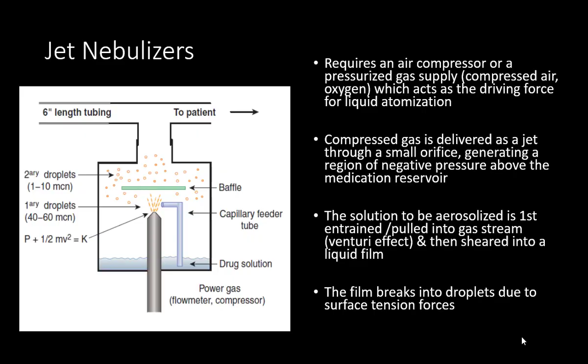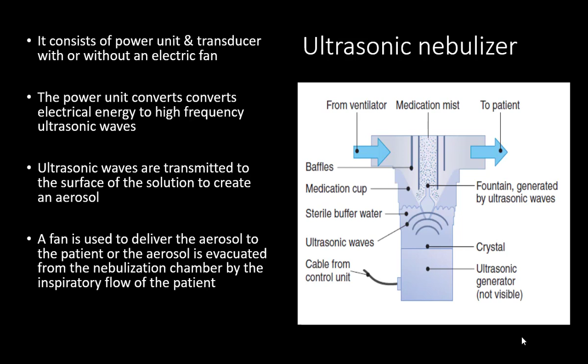Ultrasonic nebulizers need a power unit. It can have a fan or it need not have a fan. The fan is just to propel the droplets, but if a patient is on a ventilator, the propulsion can be done by your inspiratory flow. The power unit converts electrical energy to high frequency ultrasonic waves. This wave is transmitted to the solution, and that energy generates aerosols. The fan is used to deliver the aerosol to the patient, or the aerosol is evacuated from the nebulizer by the inspiratory flow of the patient.